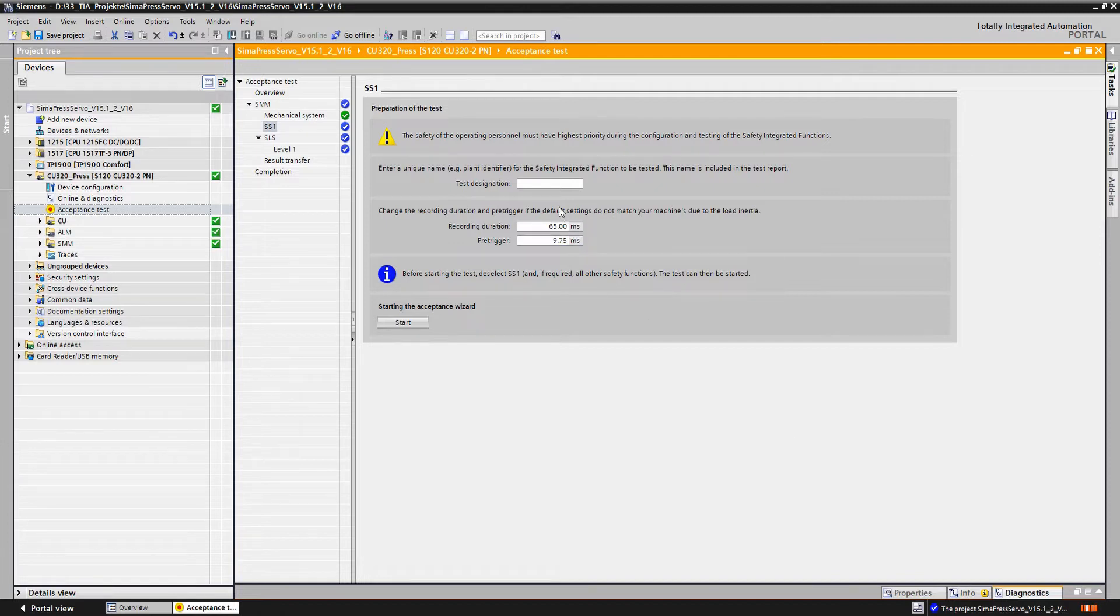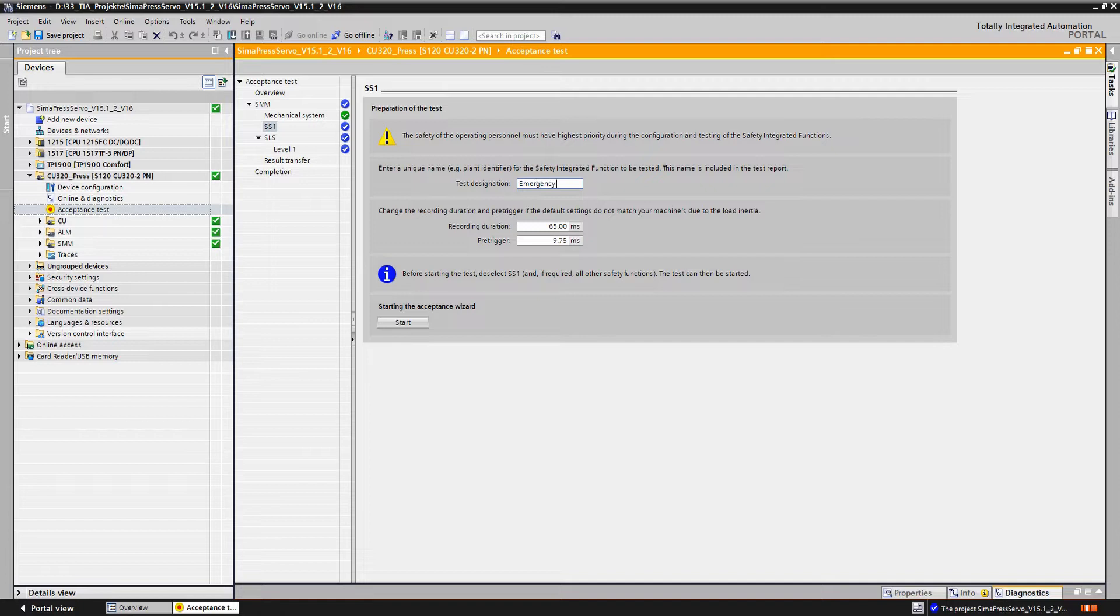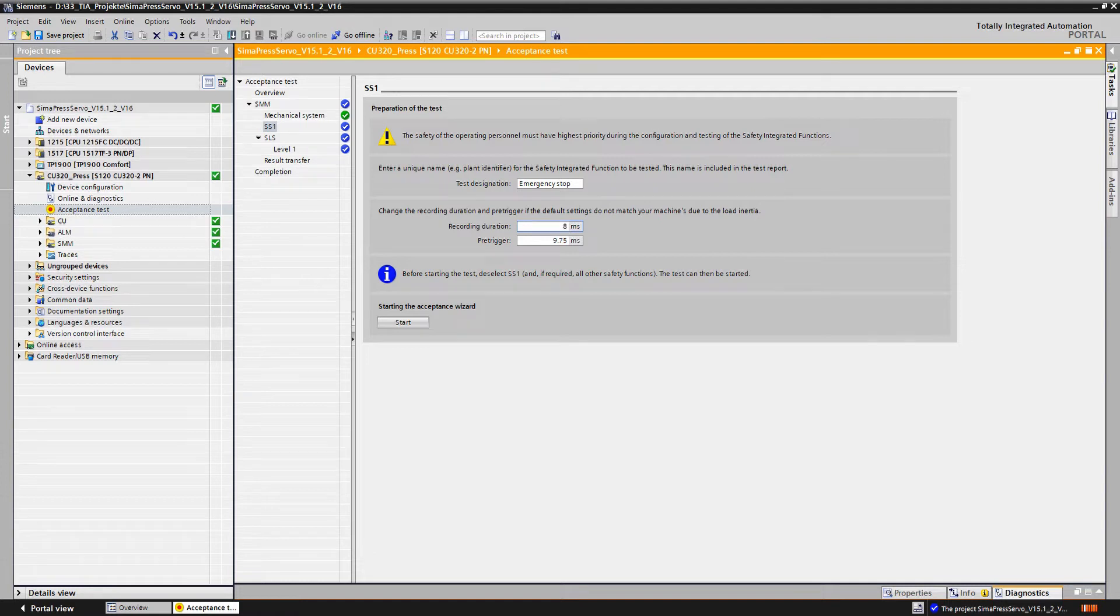For the SS1 test we first specify a test name and a trace duration and then start the test. The trace should last until the drive is completely stopped.